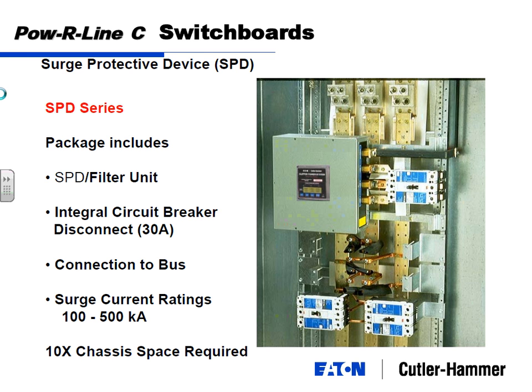Same rule applies on the SPDs or the TVSSs. Every switchboard that goes out today, just like the customer meter, there's too much value in there not to get it. The same thing applies towards the SPD. If you put in a switchboard and you're getting a service entrance, coming in from outside into your facility, it'd be foolhardy not to put in an SPD, a few $1,000 investment, an insurance policy on a $1 million building.